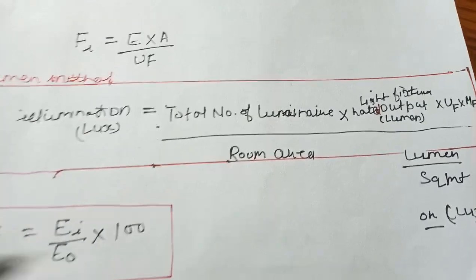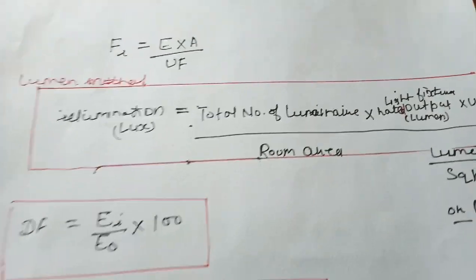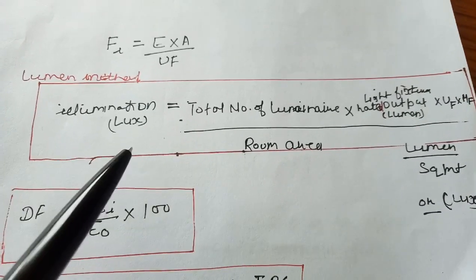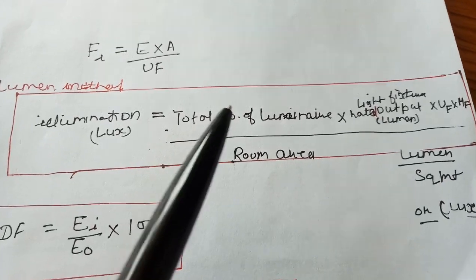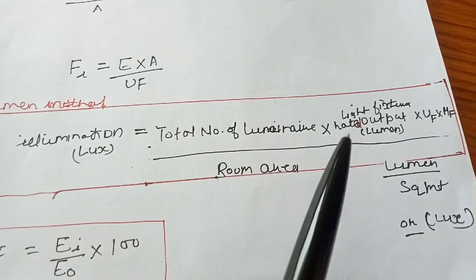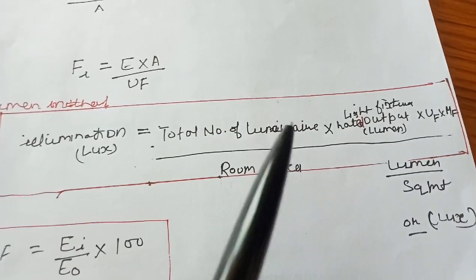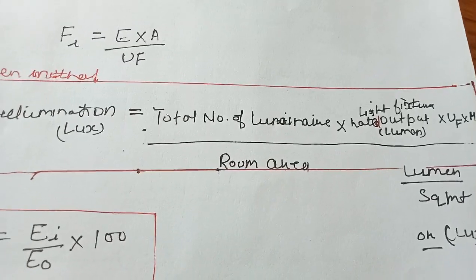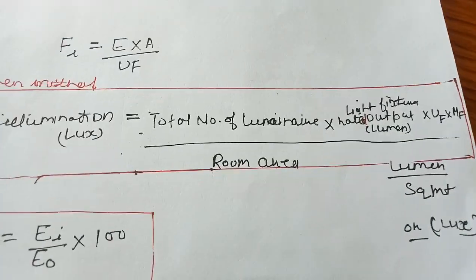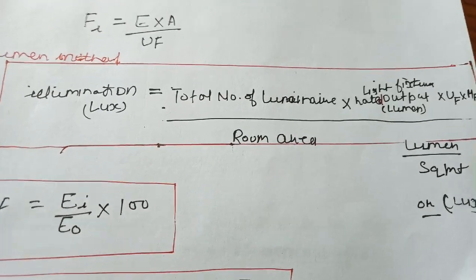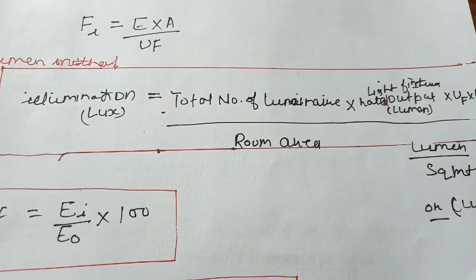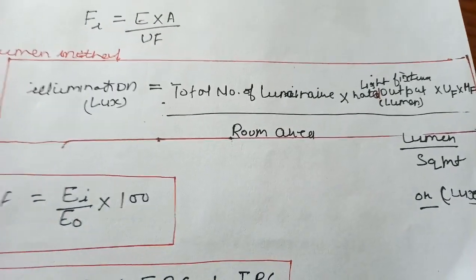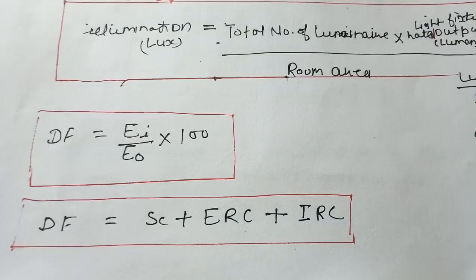The basic lumen method formula is: Illumination E equals the total number of luminaries multiplied by the rated output of one lamp (in lumens), multiplied by the utilization factor, multiplied by the maintenance factor, divided by the room area. This gives lumens per square meter. The definition of illuminance is luminous flux per area, and understanding this formula helps understand the definition.